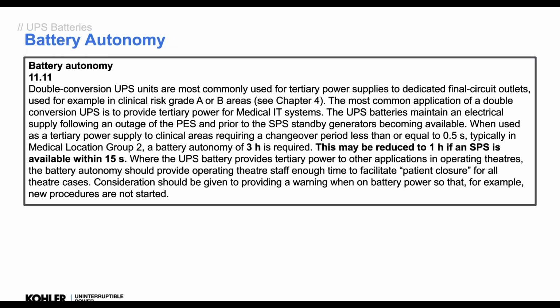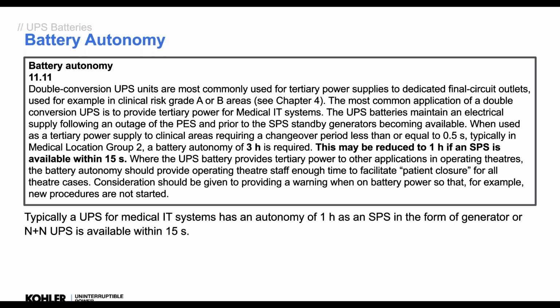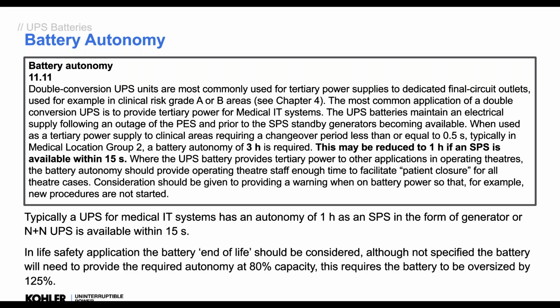So where we are using double conversion UPSs is typically 1 hour or 3 hour. Okay, 1 hour if we have a secondary power supply available within the 15 seconds in the form of another supply, a generator or another UPS. So that's typically what we have an hour. It's 3 hours if you haven't got anything else. So if it's just maybe a clinic with only one supply, no generator, then you need a 3-hour battery on the UPS.